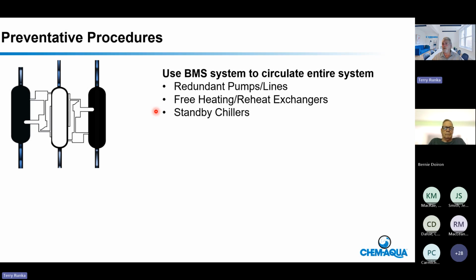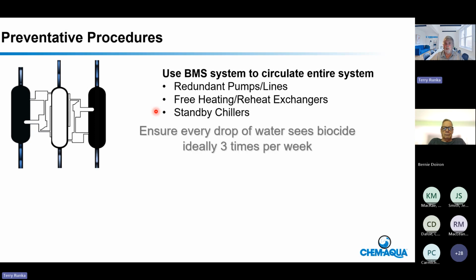We will set up the controller so it feeds the biocide and a little bit of inhibitor. We want you to do that ideally three times a week, but at least once a week, so that every drop of water sees biocide. When we do that, the Legionella concern almost instantly goes away or really reduces, because it's that standing water where it hides. Then you fire up that chiller and boom, you get the Legionella. So doing that has really helped.